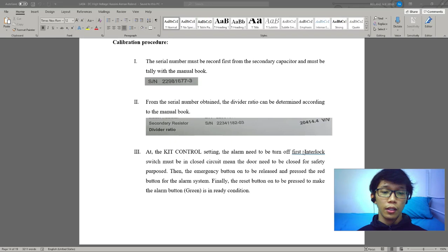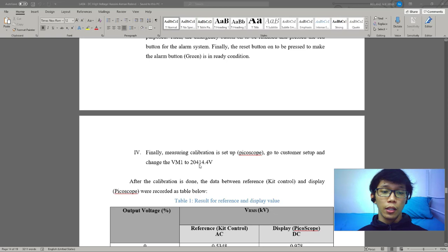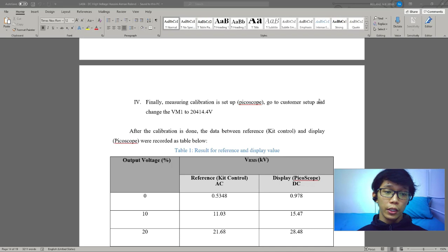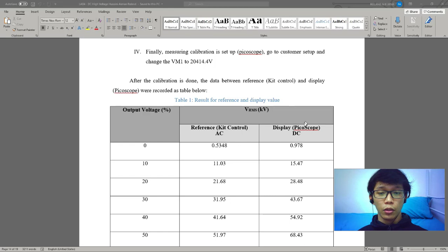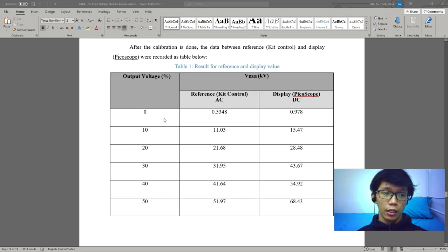And finally, the measuring calibration is set up and go to the customer setup, change the VM1 according to the divider ratio, which is 20414.4 volt. After the calibration is done, the data between reference kit control and display PicoScope were recorded as in the table below. As you can see over here, the difference between reference kit AC and display PicoScope DC. For the range, 10 will be selected as the range.